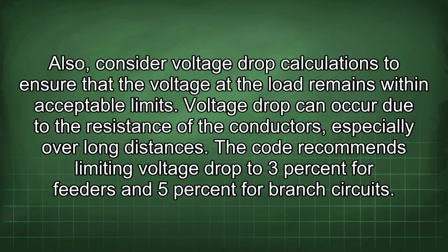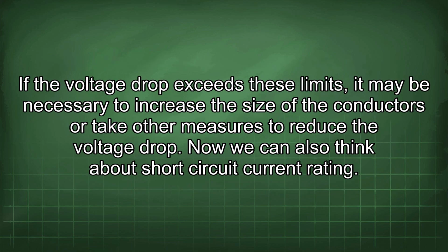Also, consider voltage drop calculations to ensure that the voltage at the load remains within acceptable limits. Voltage drop can occur due to the resistance of the conductors, especially over long distances. The code recommends limiting voltage drop to 3% for feeders and 5% for branch circuits. If the voltage drop exceeds these limits, it may be necessary to increase the size of the conductors or take other measures to reduce the voltage drop. Now we can also think about short circuit current rating.